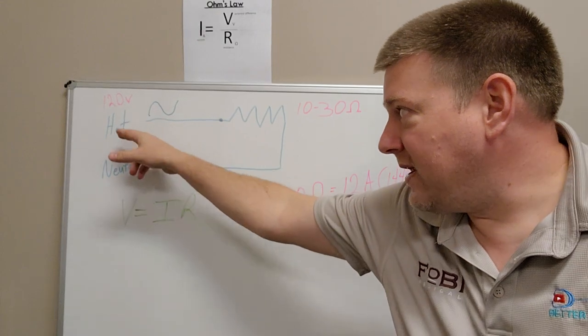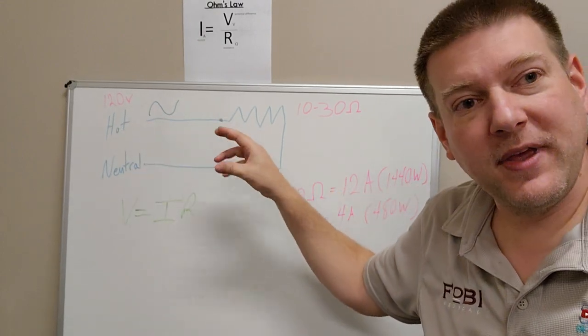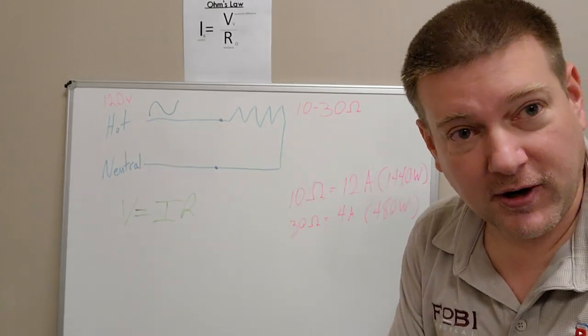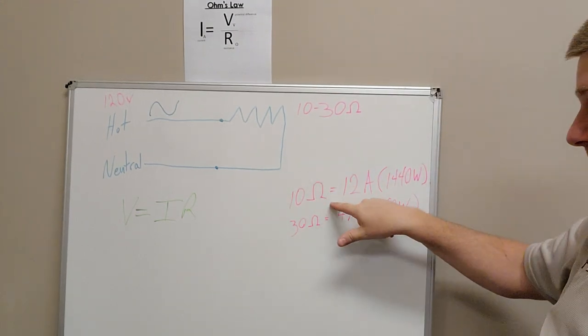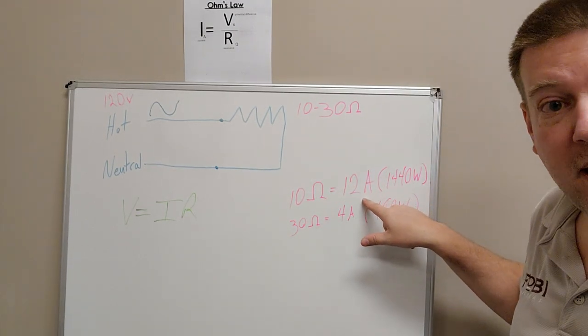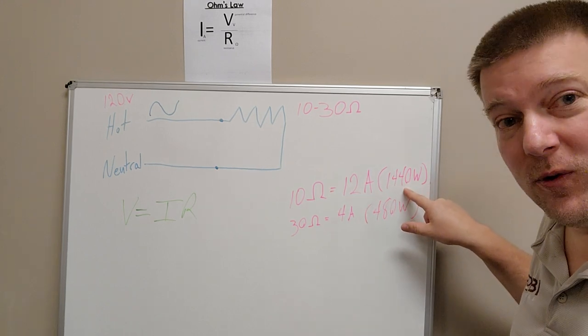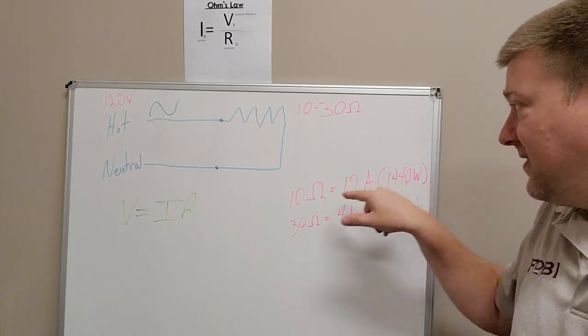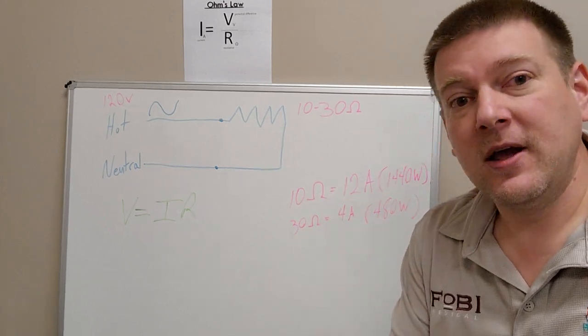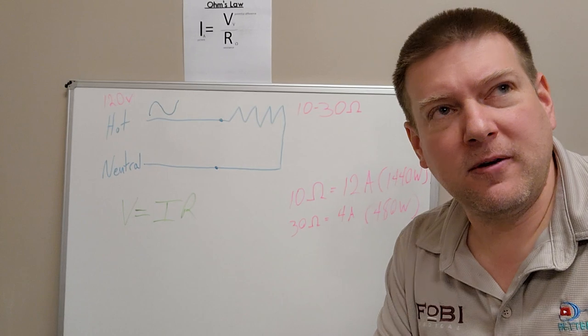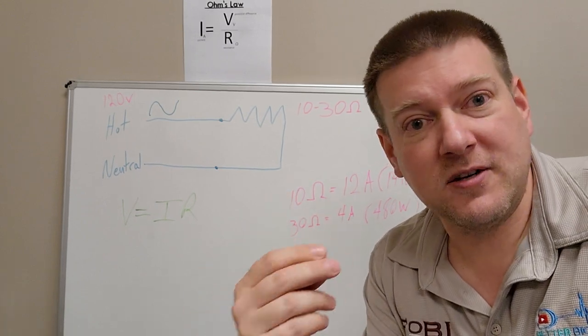When a heating element is turned on, it runs at full current, which means at 10 ohms you're getting 12 amps, which is 1440 watts. That is pretty much the max that you can get on 120 volts. This would be like a heating element for a water heater or something like that.